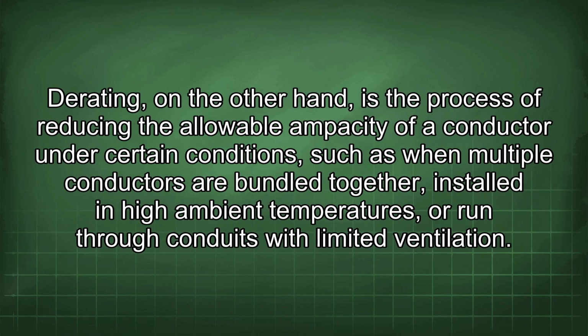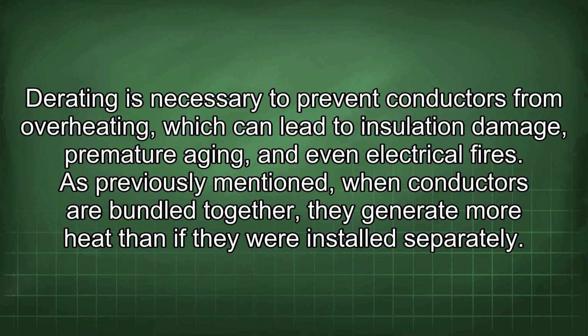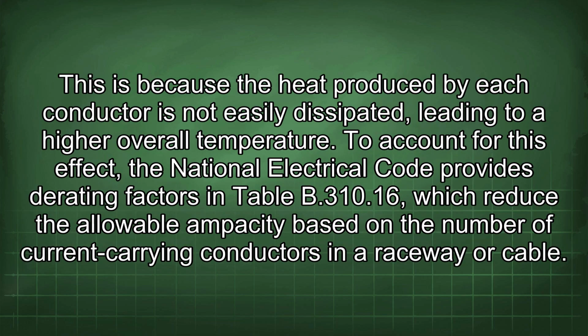Derating, on the other hand, is the process of reducing the allowable ampacity of a conductor under certain conditions, such as when multiple conductors are bundled together, installed in high ambient temperatures, or run through conduits with limited ventilation. Derating is necessary to prevent conductors from overheating, which can lead to insulation damage, premature aging, and even electrical fires. As previously mentioned, when conductors are bundled together, they generate more heat than if they were installed separately. This is because the heat produced by each conductor is not easily dissipated, leading to a higher overall temperature.